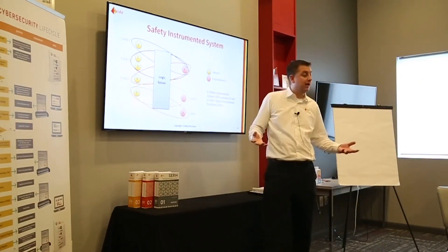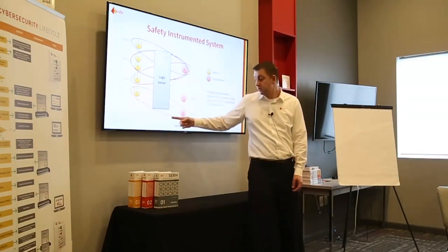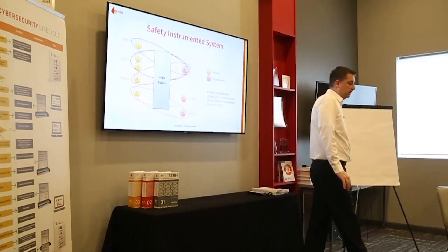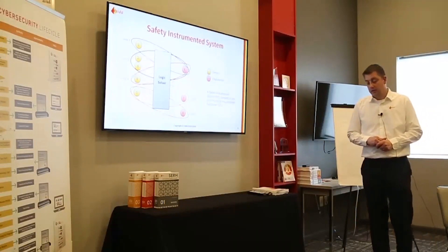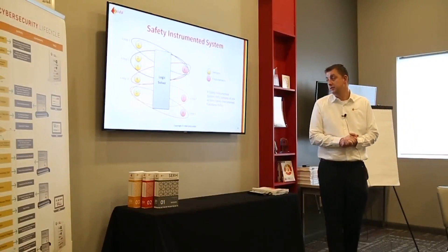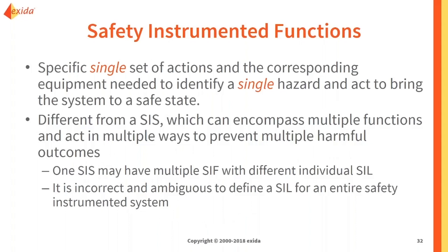For sensors, we could have a low pressure measurement doing one thing and a high pressure measurement doing something else with the same sensor, or overfill and dry run measured with the same level instrument — different actions, but the same instrument. So when we talk about safety instrumented functions, there is always a single set of actions and corresponding equipment to identify a single hazardous event and bring it to safe state. We assign SIL levels to individual SIFs, not to the entire safety instrumented system.